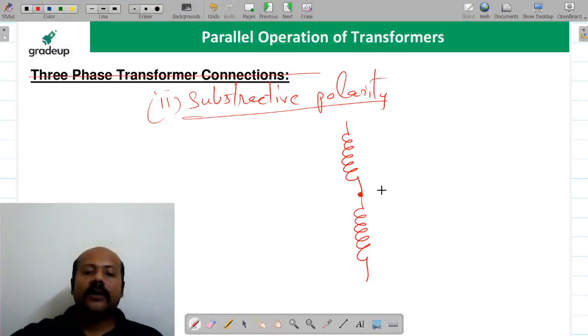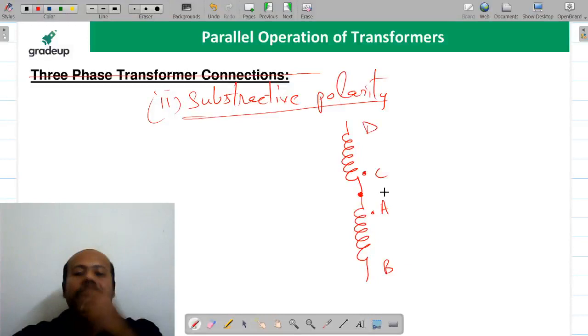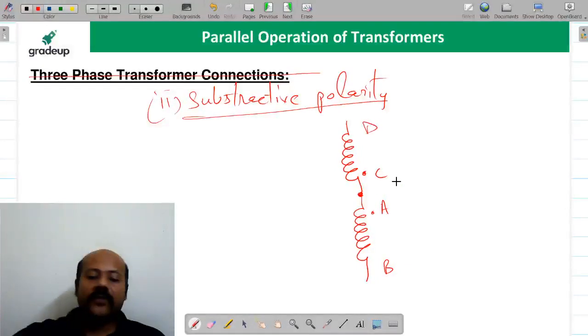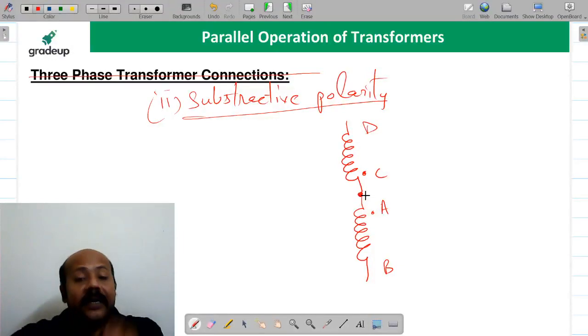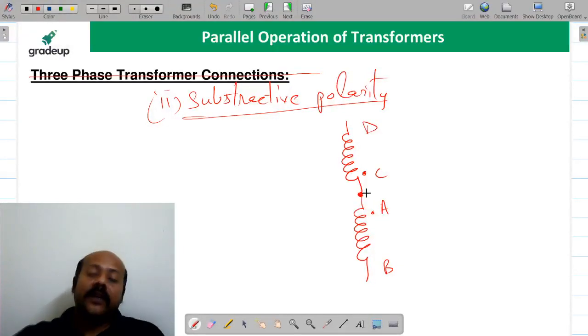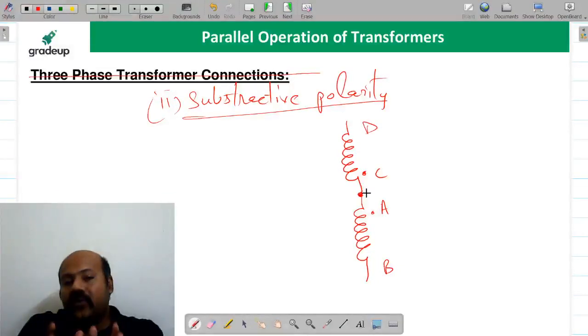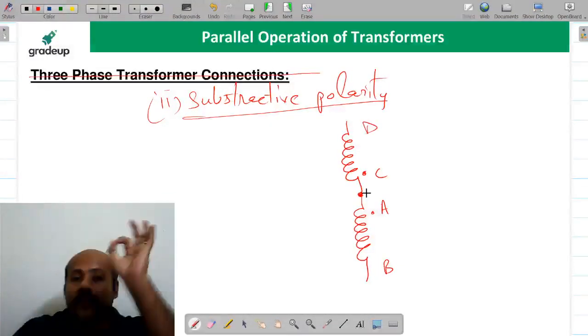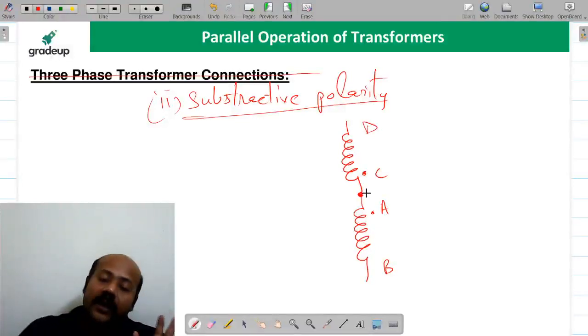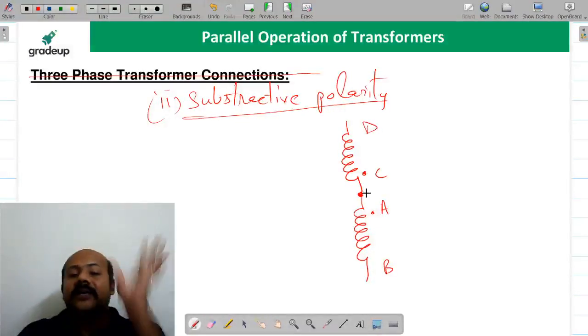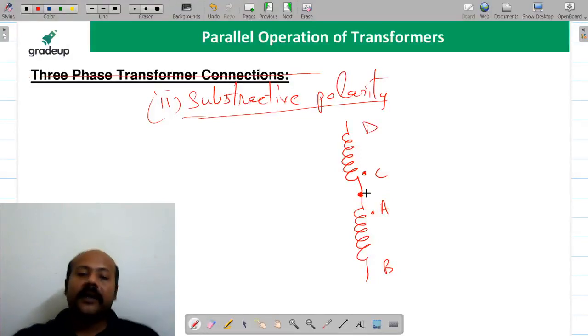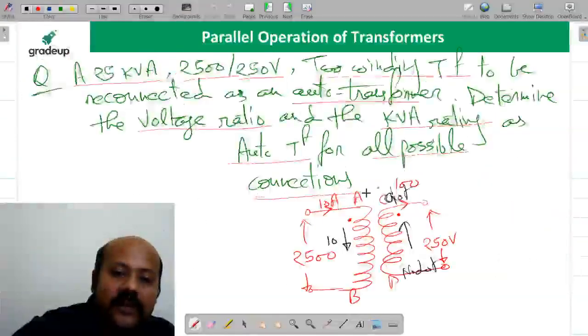Suppose this is AB, and this we are taking as CD reversed. We have reversed the CD winding. I hope it is clear. Now this is going to be the subtractive polarity, but the current sense is not going to change. Whenever you reconnect any two-winding transformer as an autotransformer, you must remember this fundamental principle: the current sense in the winding does not change. That is very important. So go back to the previous diagram.